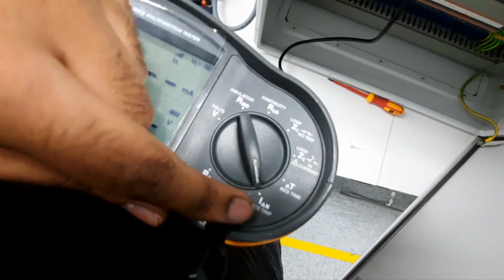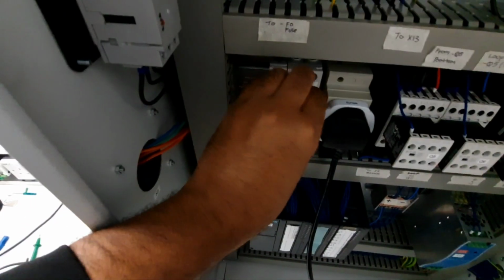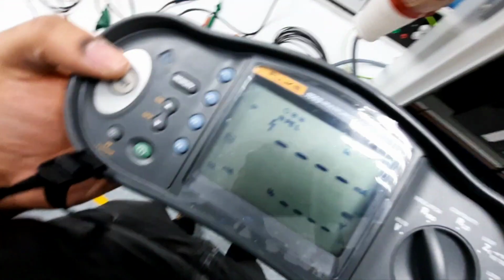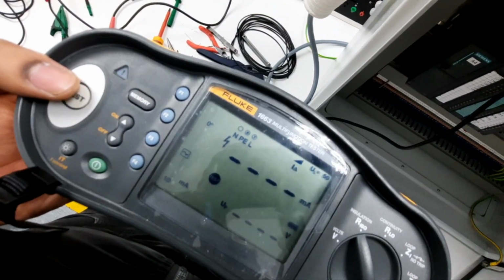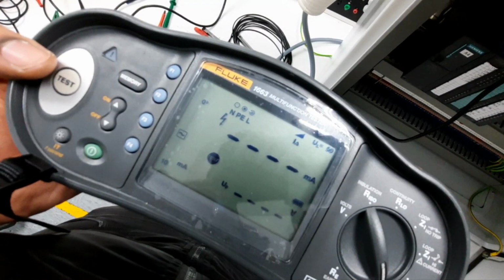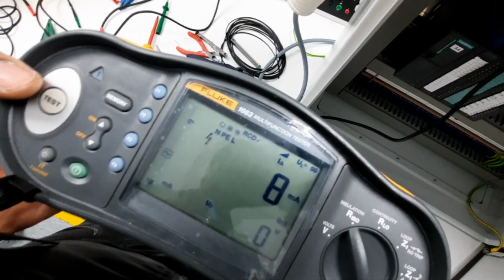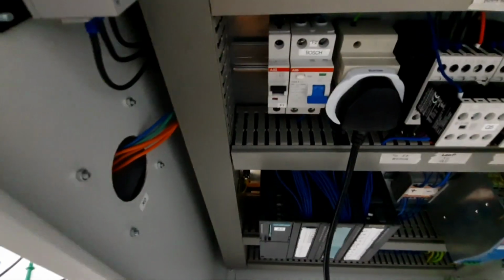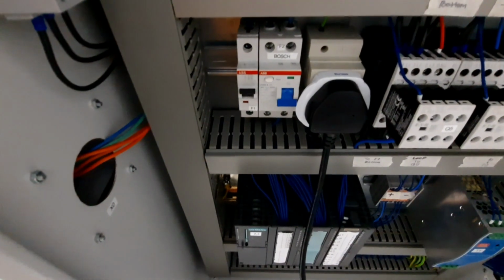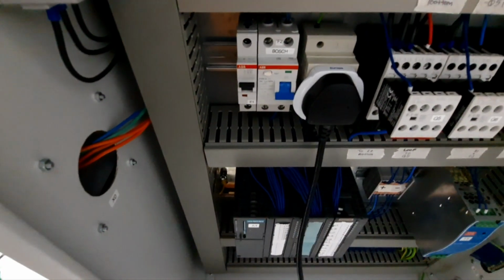Okay, so now we're going to test the current trip. We have to turn this on back again and then test again. Okay, so it tripped and it's 8 milliamps. So the design for RCD is 10 milliamps, so the RCD must trip at less than 10 milliamps. So you got 8 milliamps, which is okay, and your contact voltage is still 0.